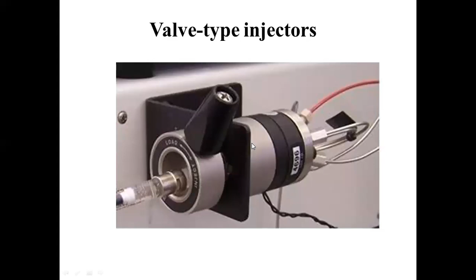So take the sample in the hypodermic syringe, penetrate the needle into the sample port, rotate the knob towards the load, right? Then you dispense the liquid which is present in the syringe. After dispensing, you rotate the knob towards the injection mode. Now the sample has joined the mobile phase front. So the mobile phase is now taking away the solute molecules which were present in the sample in the injection port. So this is the valve loop injector, what I had shown while explaining gas chromatography.